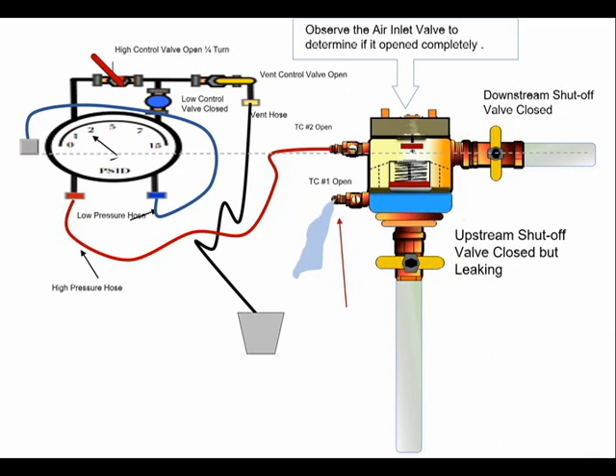If this balance cannot be achieved, the air inlet valve opening point cannot be measured until the upstream shutoff valve can be re-closed, repaired, or replaced.